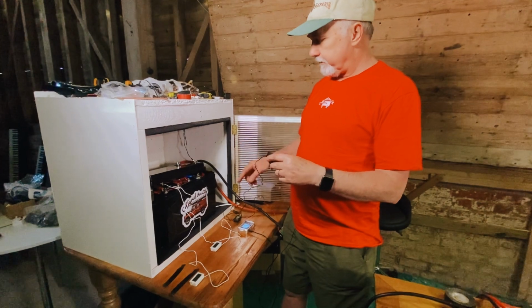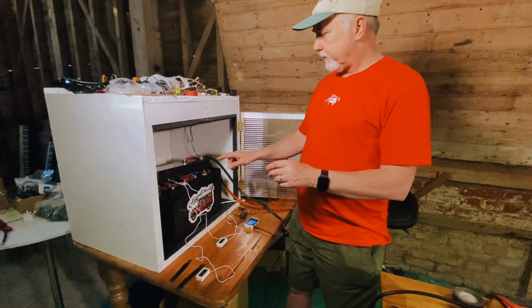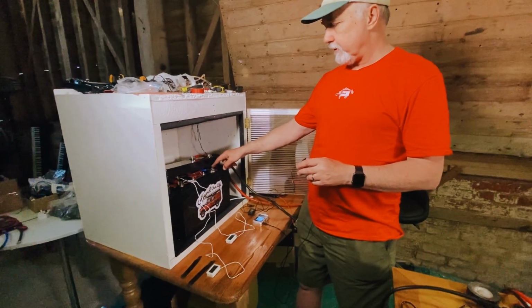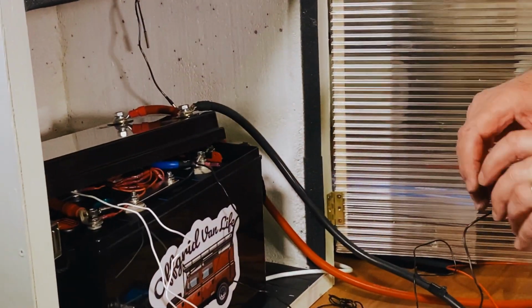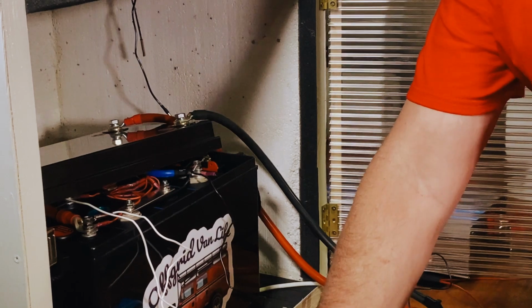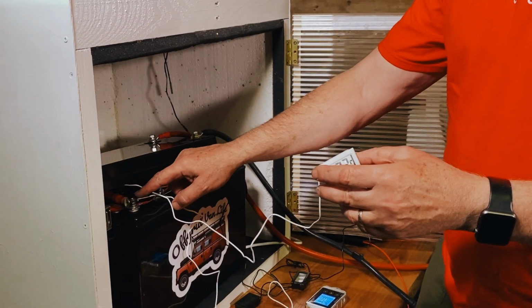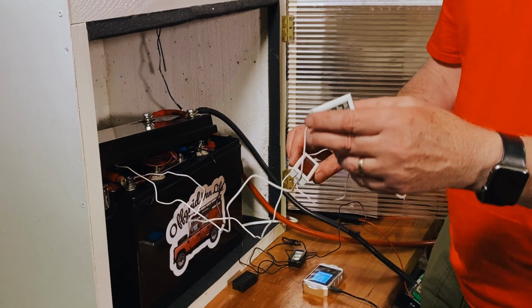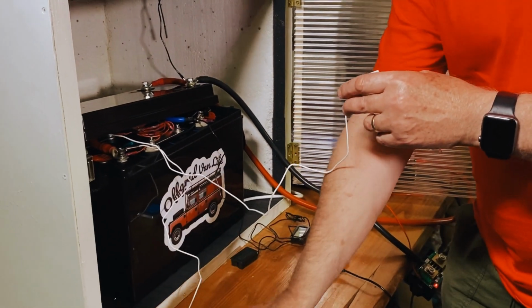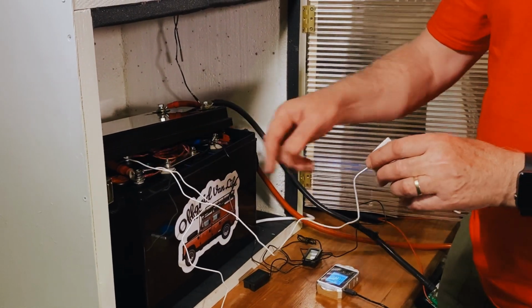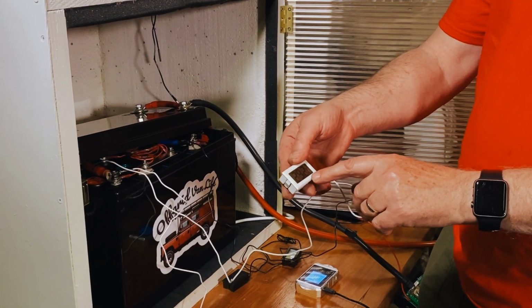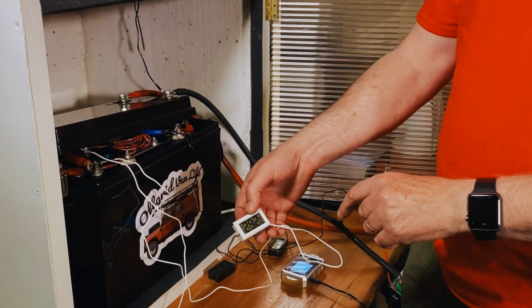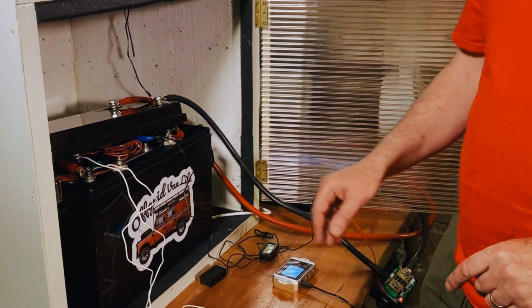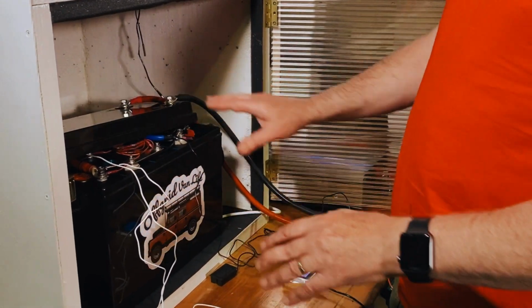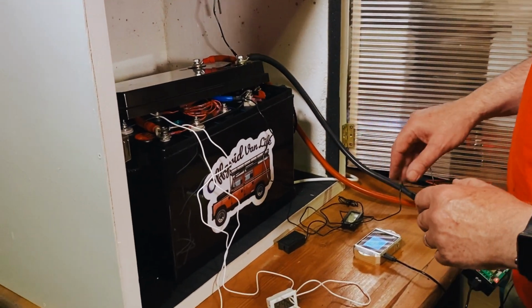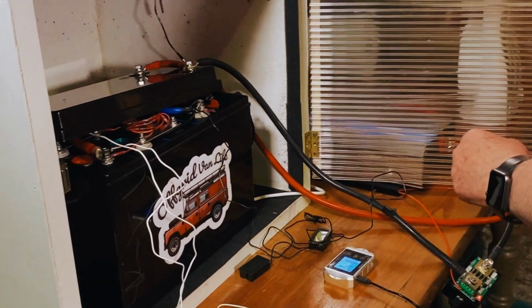We have put a temperature probe onto the main negative of the cell, and one on the main positive, reading 29.5. There's another probe on the main positive cable inside there, so 3 probes inside the box. We also have the BMS itself, and we're bringing these cables out.